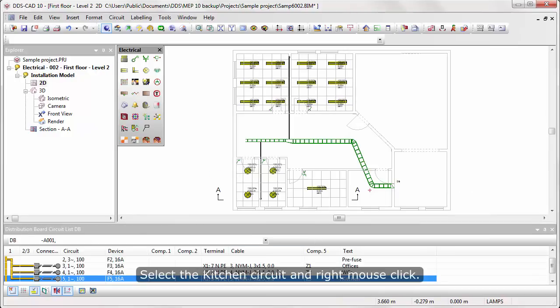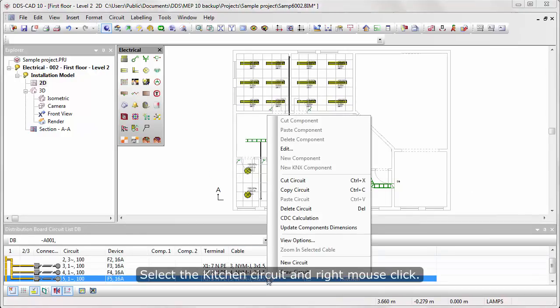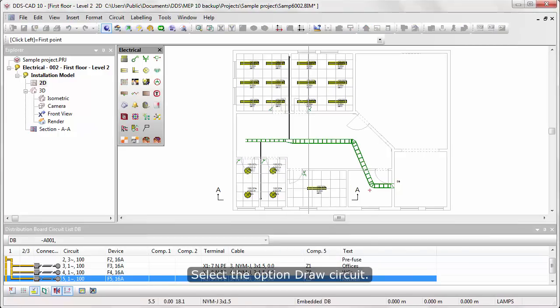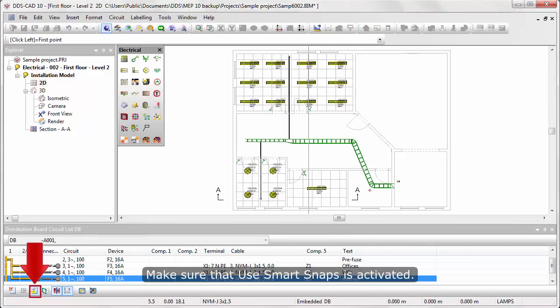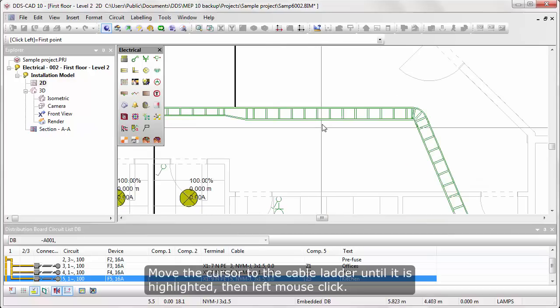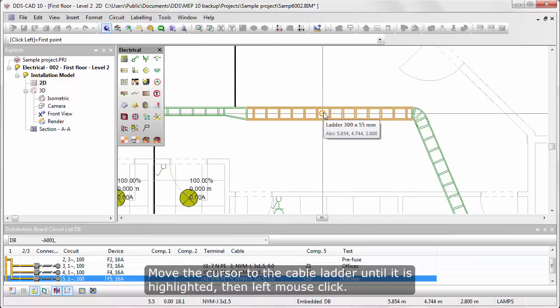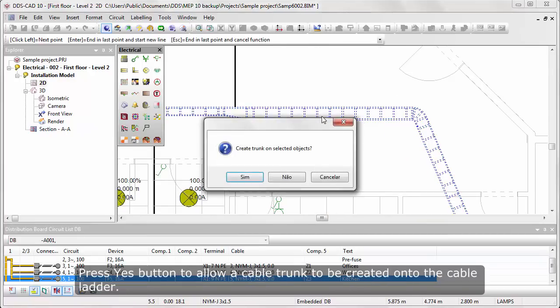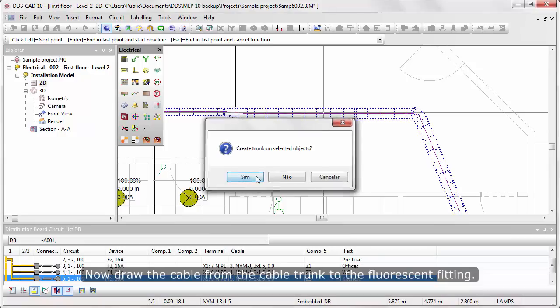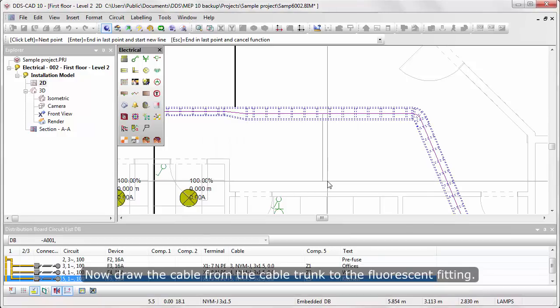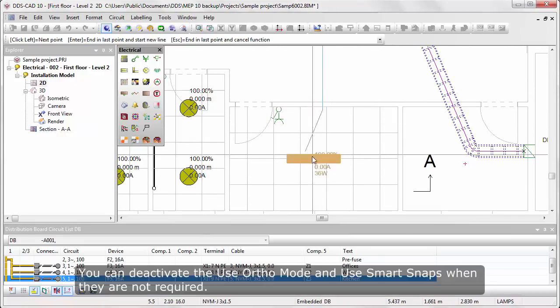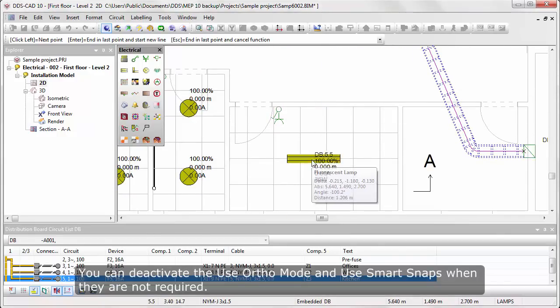Select the Kitchen Circuit and right mouse click. Select the option Draw Circuit. Make sure that Use Smart Snaps is activated. Move the cursor to the cable ladder until it's highlighted and left mouse click. Press Yes button to allow a cable trunk to be created onto the cable ladder. Now, draw the cable from the cable trunk to the Fluorescent Fitting.